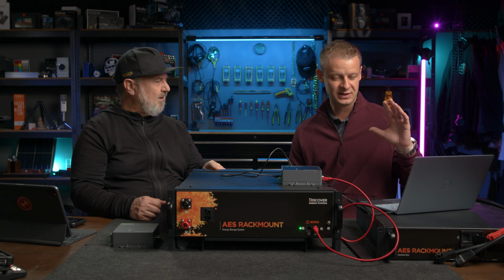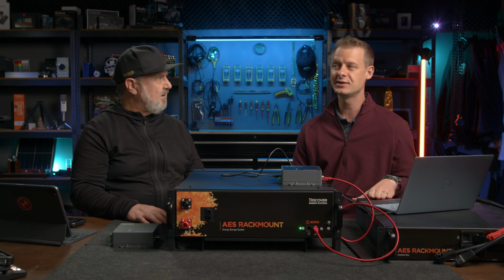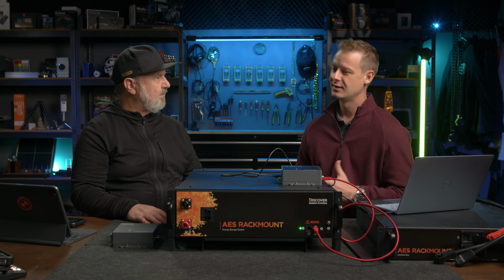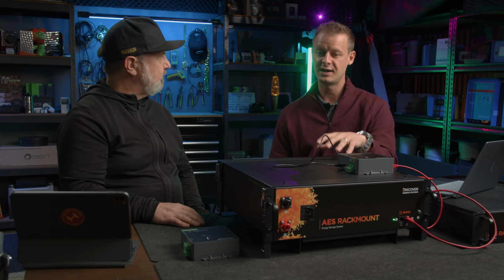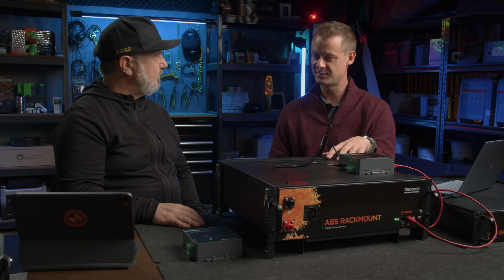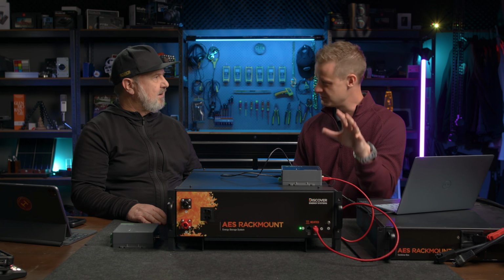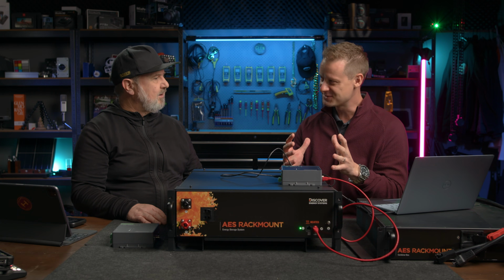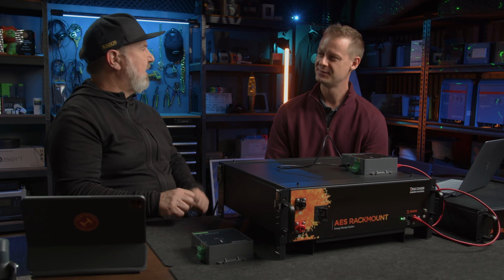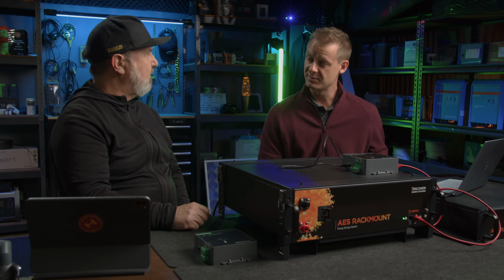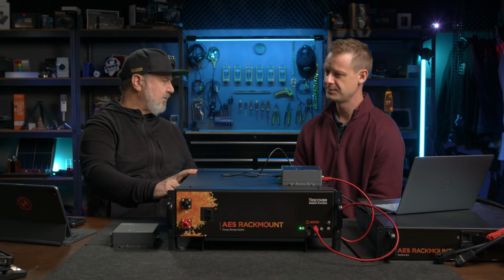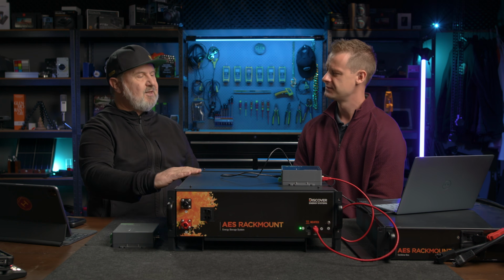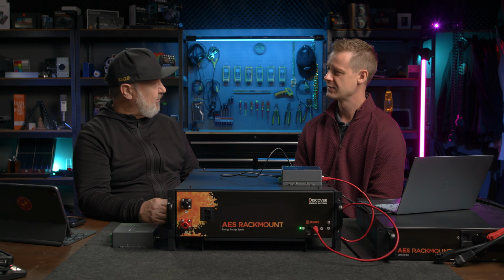The combiner box is configured for 6, though there are ways to expand that to 8. The communications for these batteries can actually stack up to 36 batteries with closed loop communications or managed BMS configurations. So multiple combiner boxes - you could do multiple combiner boxes, a stack of 6, up to a total of 36.